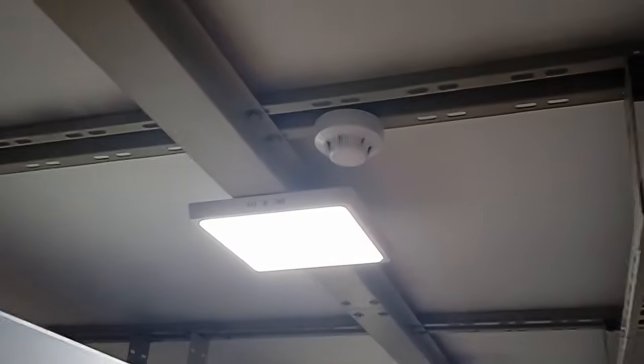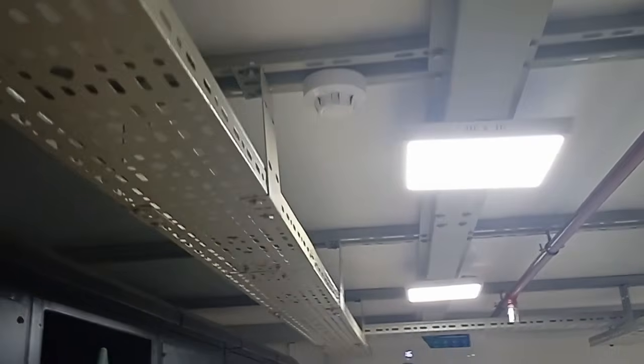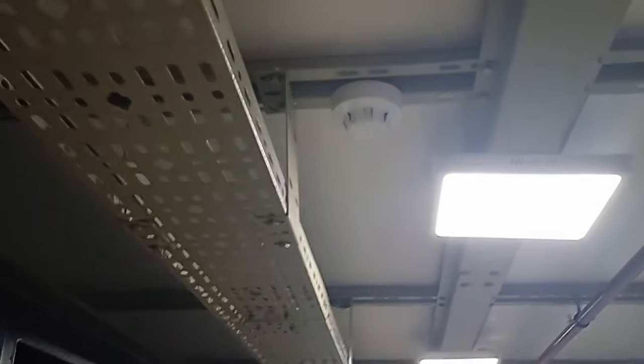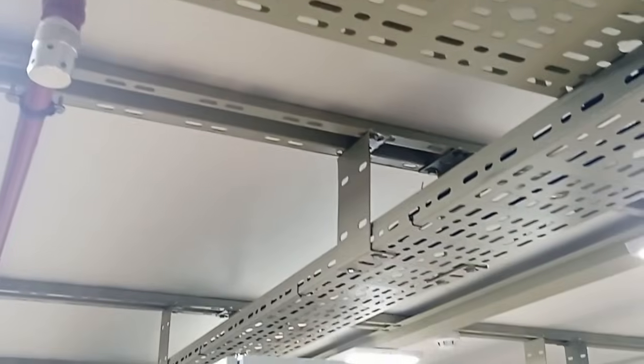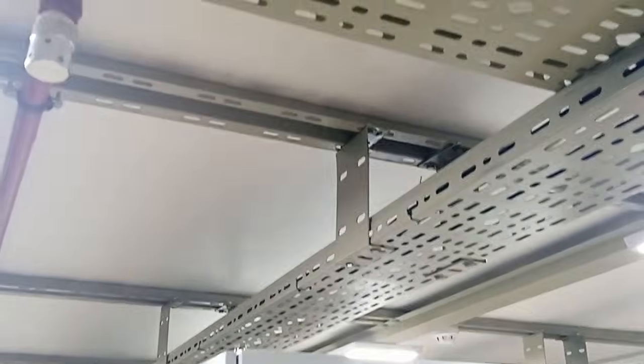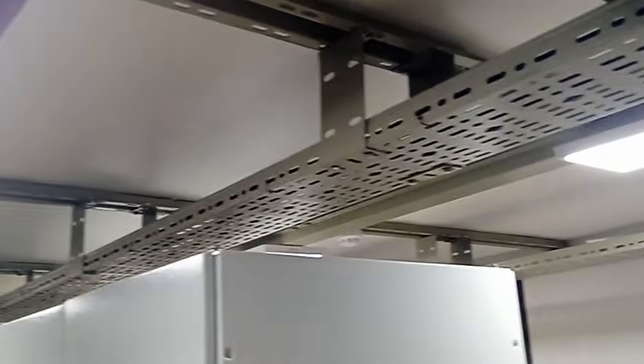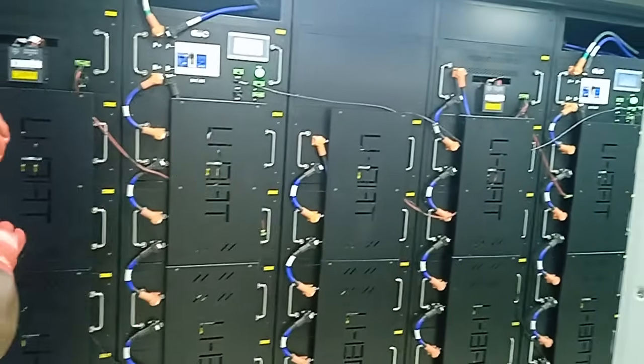This first smoke detector will detect the smoke, and when it detects the smoke, it sends the information to the controller, which I will show you later in this video. Once the controller receives the information, it will wait till the second smoke detector detects the smoke also. Once the second smoke detector detects the smoke, it will send information to the control panel that this fire is serious. The control panel will now trigger the actuator to discharge the gas. And once the actuator punches the gas cylinder, it will discharge the gas through this pipe and it will suppress the fire inside this place immediately.